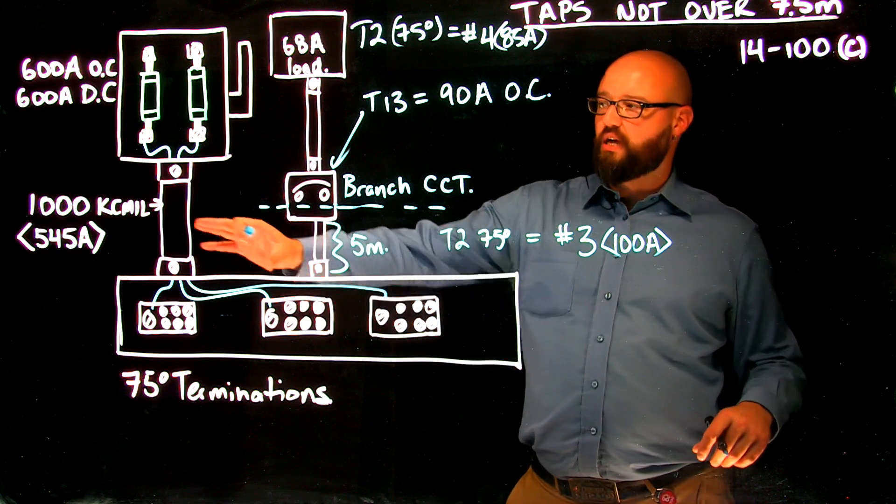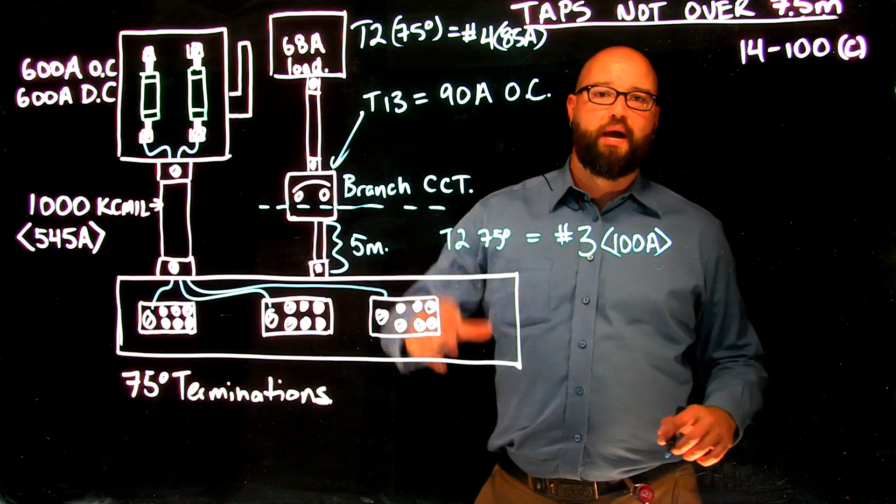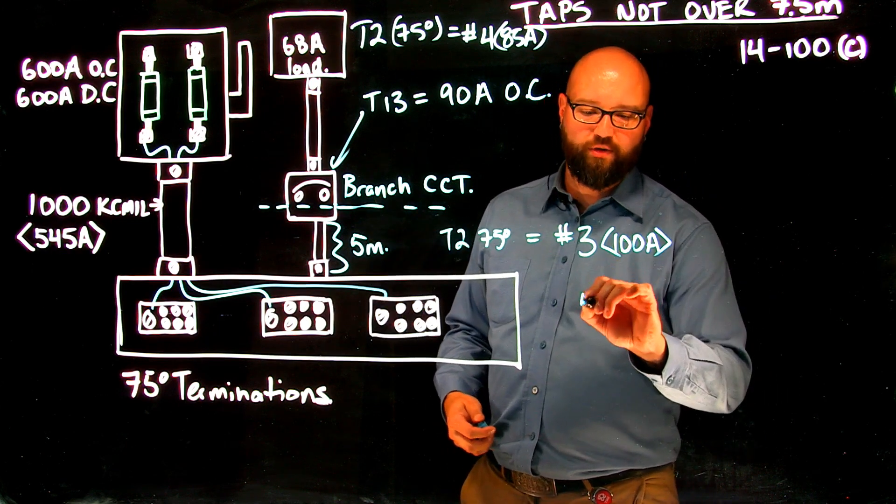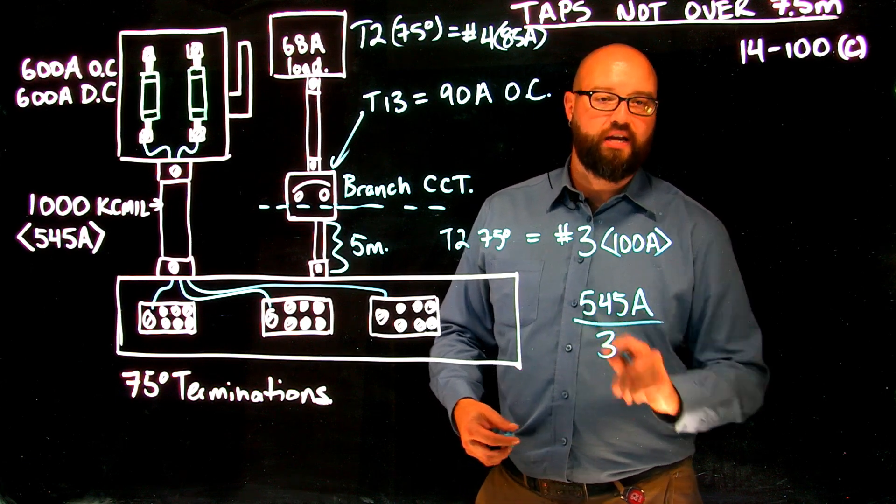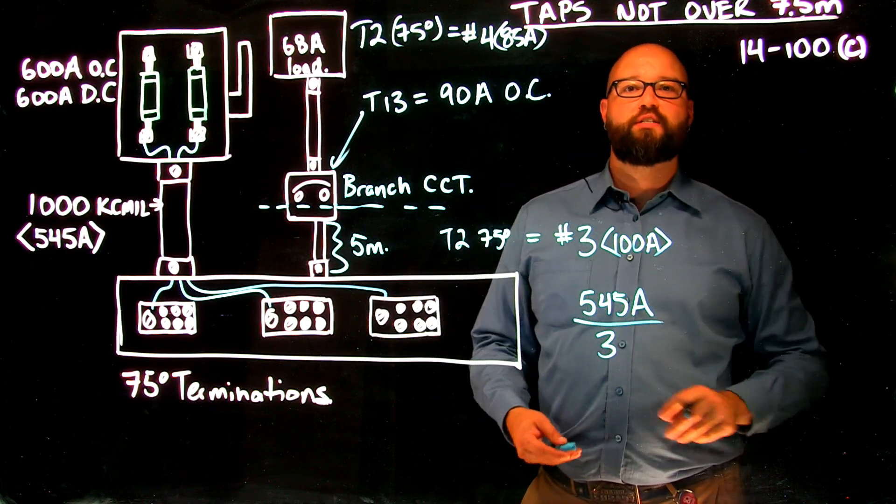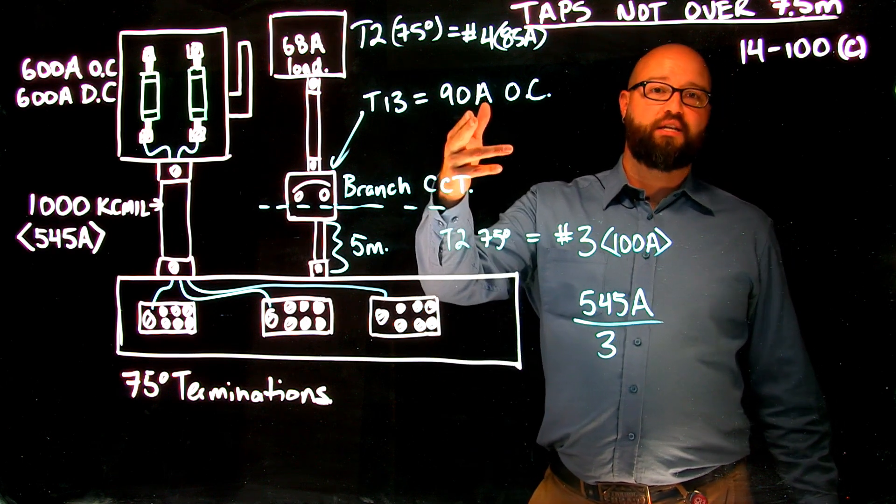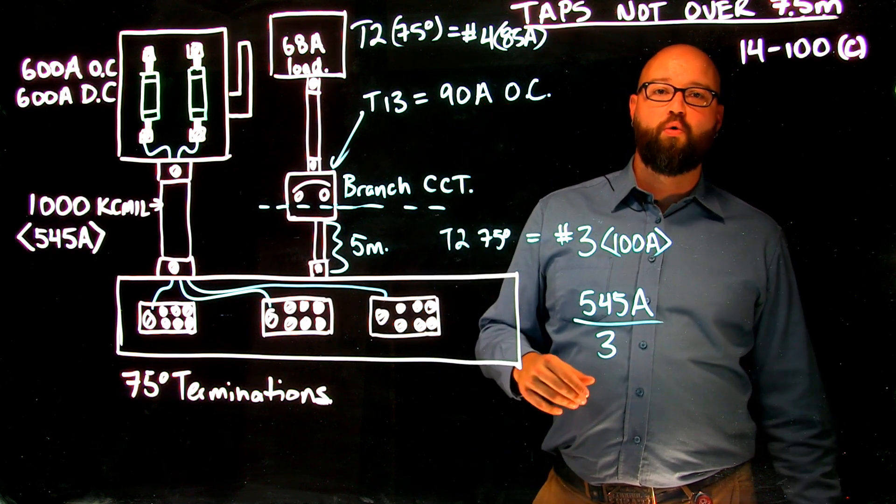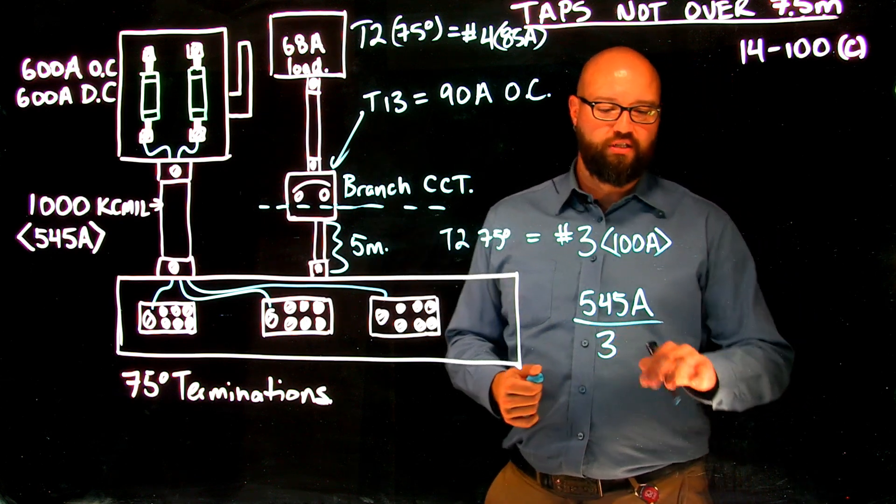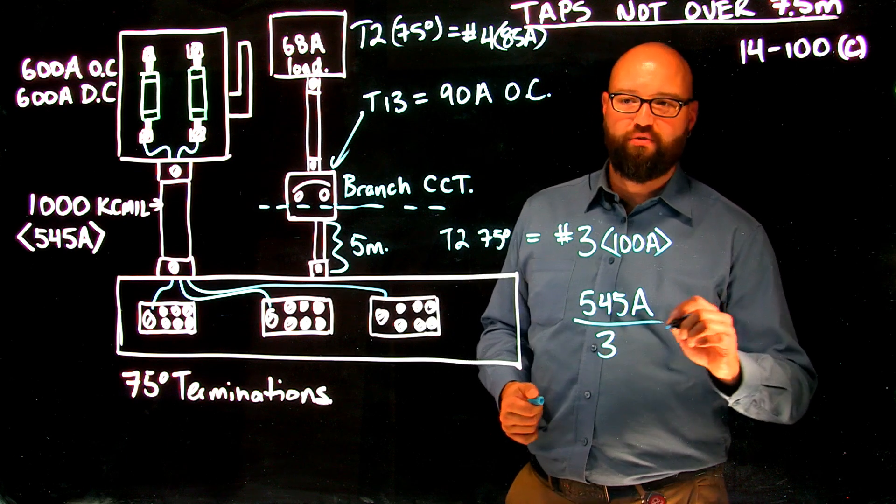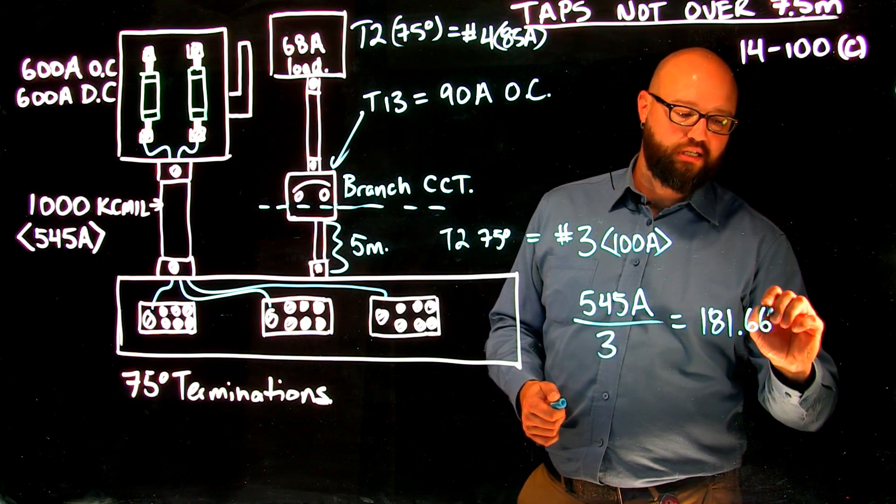The second is I'm going to go over to my feeder conductor, which is a thousand KC mil. I'm going to take the ampacity of that feeder conductor, which is 545 amps, and I'm going to divide it by 3 because it tells me 14100C. My tap is either slightly larger than the ampacity of my overcurrent or one-third the ampacity of my feeder conductor, which in this case 545 divided by 3 ends up at 181.667 amps.